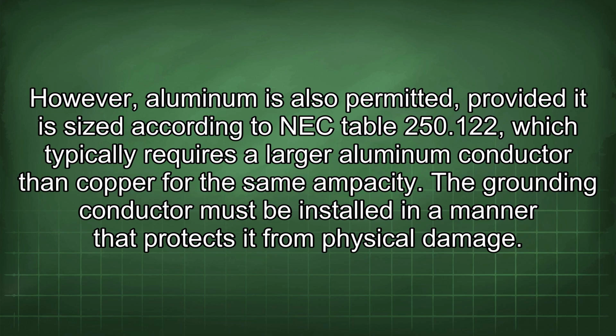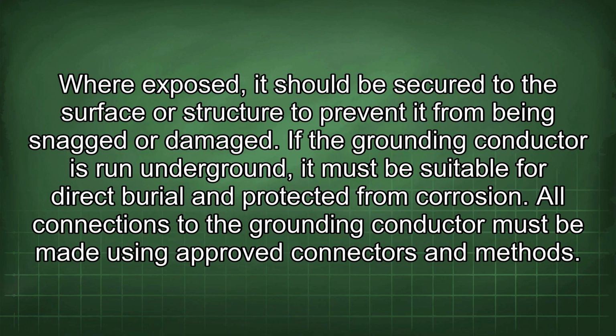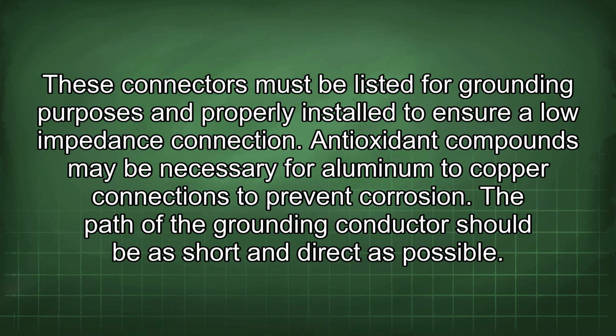The grounding conductor must be installed in a manner that protects it from physical damage. Where exposed, it should be secured to the surface or structure to prevent it from being snagged or damaged. If the grounding conductor is run underground, it must be suitable for direct burial and protected from corrosion. All connections to the grounding conductor must be made using approved connectors and methods. These connectors must be listed for grounding purposes and properly installed to ensure a low impedance connection. Antioxidant compounds may be necessary for aluminum to copper connections to prevent corrosion.